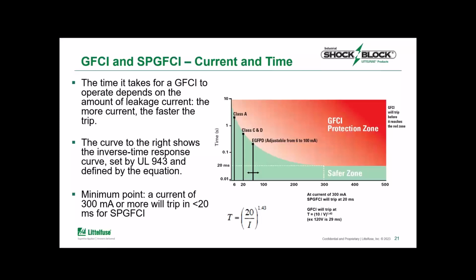So while it may seem that the special purpose GFCI is not as safe due to that higher pickup level, we're talking 20 versus 6, it's not necessarily true. In a way, the special purpose GFCIs are a bit more proactive than the class A counterpart due to that additional ground monitor interrupter function.